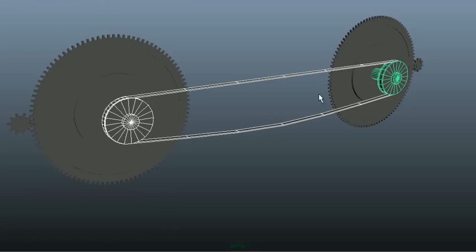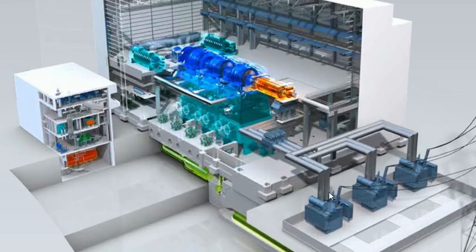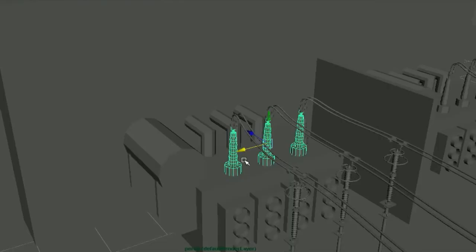So the same concept applies in electrical systems — to reduce losses, voltage must be increased. In the mechanical system, the belt thickness must be greater because the stretch on the belt is much higher; similarly in the electrical system, if we increase the voltage, we must increase the thickness and number of insulation discs because the voltage stress is much higher. If we increase the voltage to 400 kV, known as an EHV system, we must use a double conductor per phase because at that high voltage the air around the conductor starts to ionize — this is called corona loss.